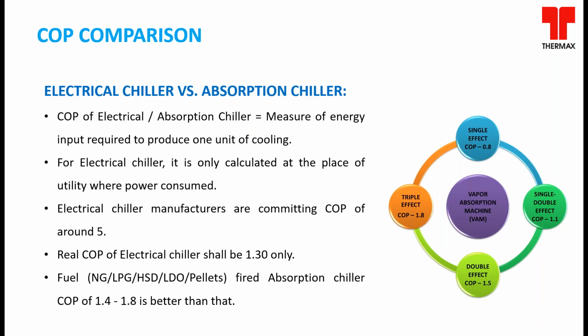So a layman can get confused, wherein he may wonder why there is a technology which is the electrical chiller, which has a COP of 5, and an alternate technology, the absorption technology, has such a low COP, and why would somebody need to go and look at the low COP technologies. One point which needs to be kept in mind is that COP is a term indicating the efficiency of the equipment, not of the entire system, or it doesn't take into consideration the source of energy. So everything has to be taken to the source of energy to arrive at a meaningful comparison.